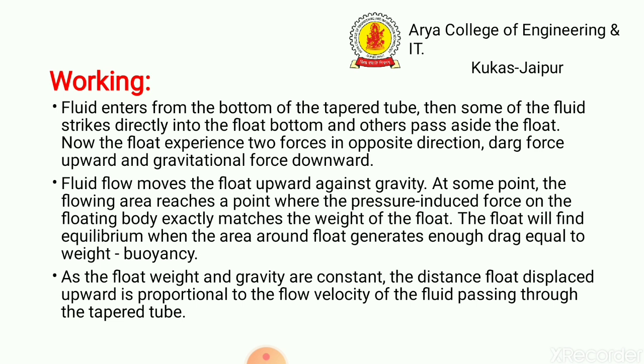The float finds equilibrium when the area around the float generates a drag equal to the weight — this is called buoyancy. Since the float weight and gravity are constant, the distance the float is displaced upward is proportional to the flow velocity of the fluid passing through the tapered tube.